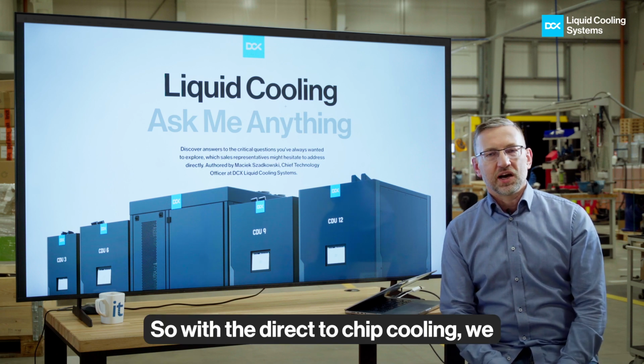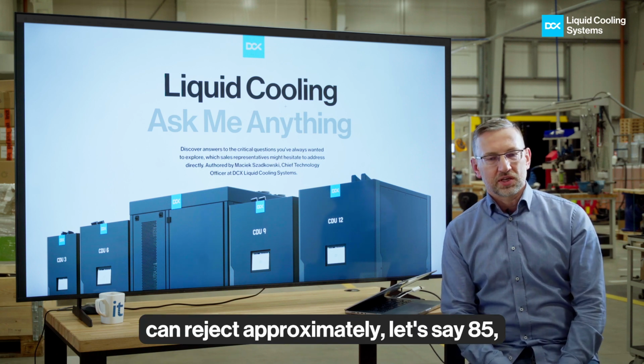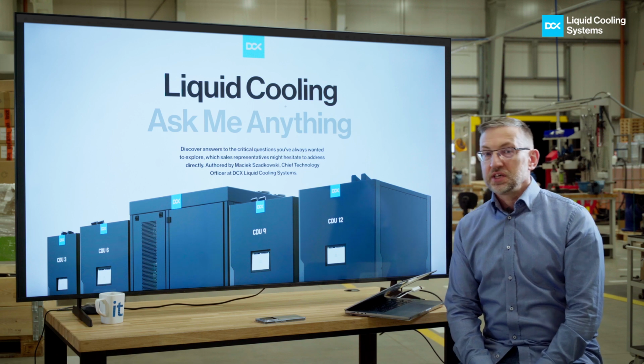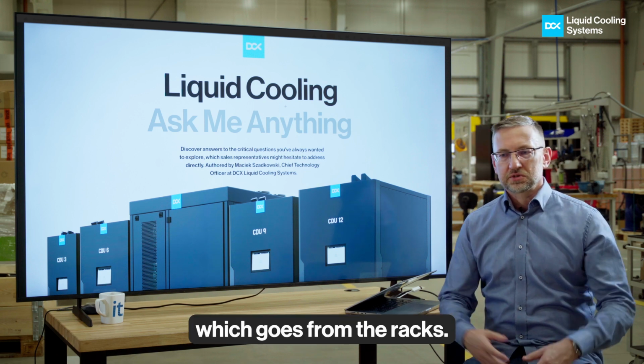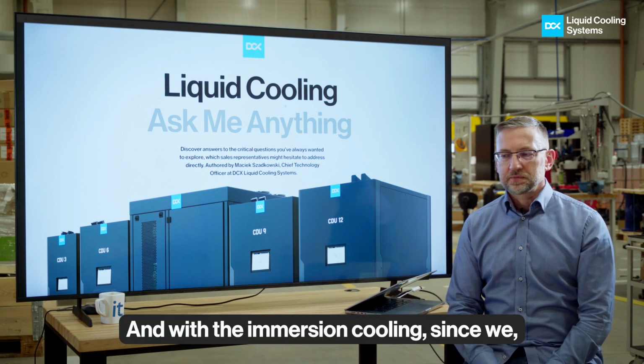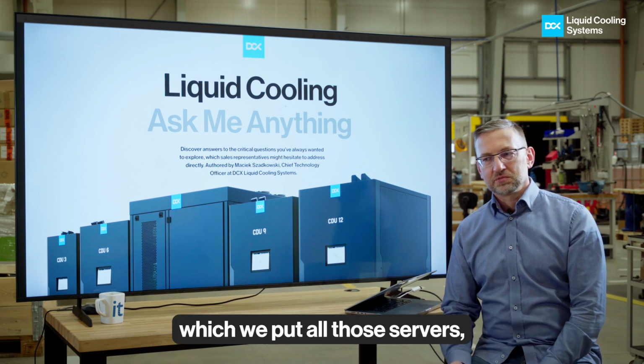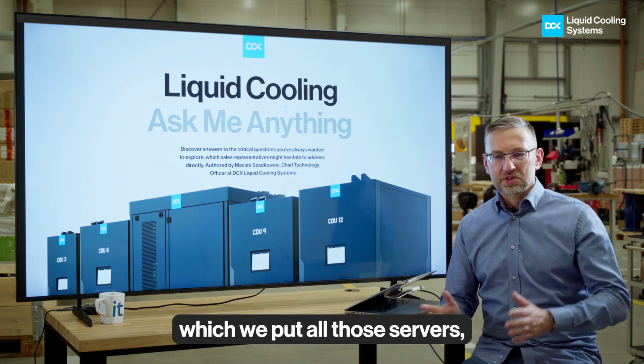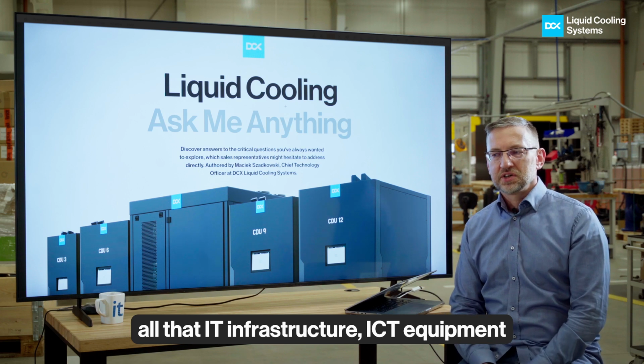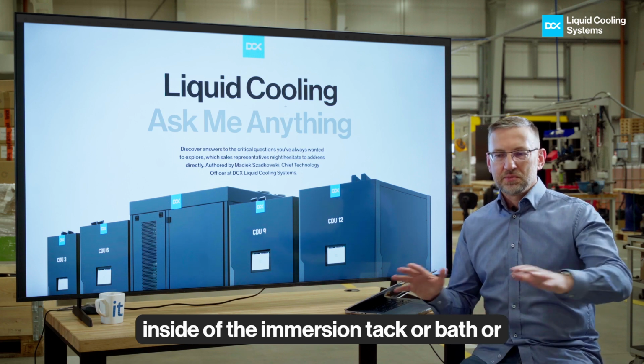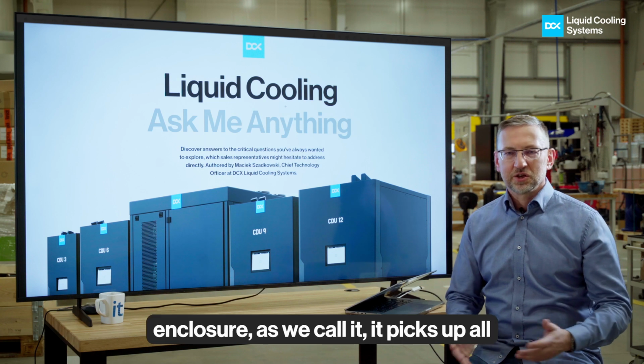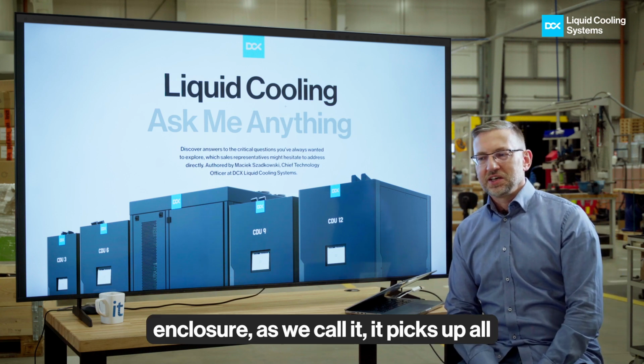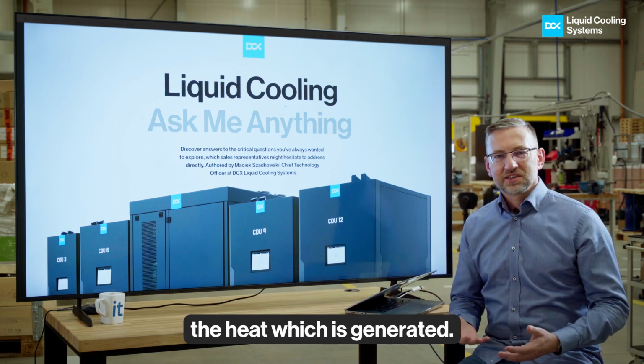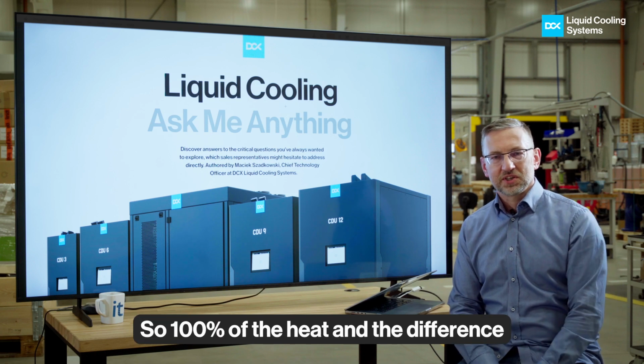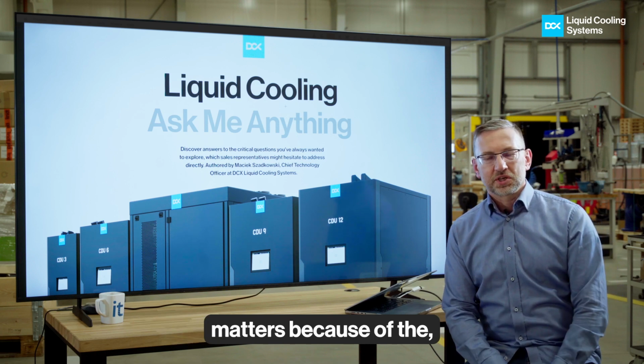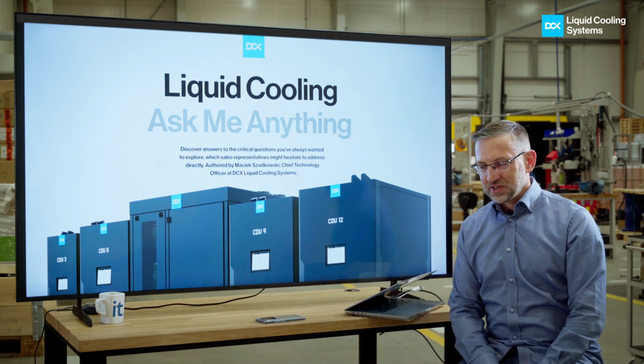So with direct-to-chip cooling, we can reject approximately, let's say, 85, even 90% of the heat which goes from the racks. And with immersion cooling, since we put all that IT infrastructure, ICT equipment, inside of the immersion tank or bath or enclosure, as we call it, it picks up all the heat which is generated, so 100% of the heat. And that difference matters for a few reasons.